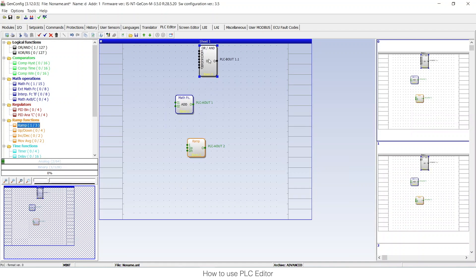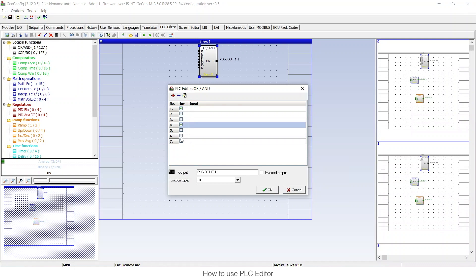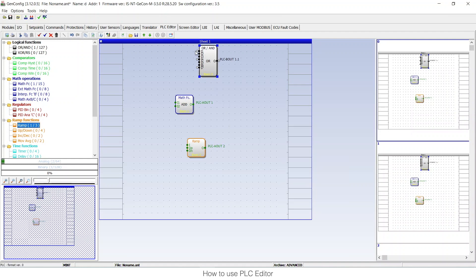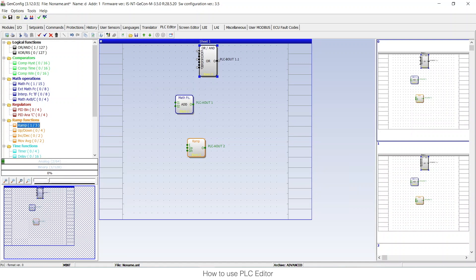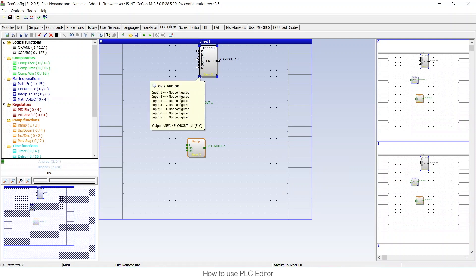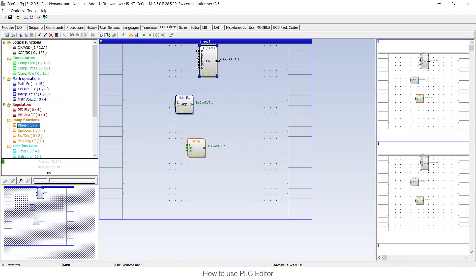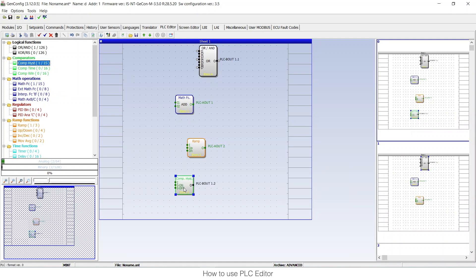I can also invert some of the inputs and the output. When you invert the output you can see a white circle on the input or output, which means it is inverted — in Comap white means it's inverted and will do the opposite of what is expected. The black color means it is a binary input or binary output, and the green color means it is an analog input or analog output. There are also comparison blocks that are a mix, having analog inputs and a binary output.